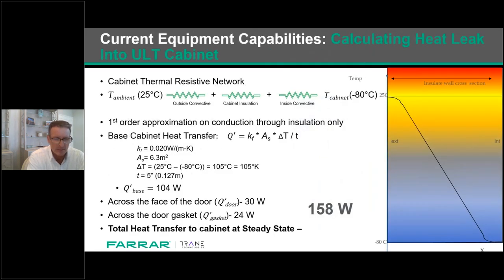So on this slide, we're going to go into the weeds. Where are we when we start calculating heat load? The following calculations were made from a 700 liter or 25 cubic foot ULT freezer. And this is where, you see at the top, we take into consideration the outside convection plus the cabinet insulation plus the inside convection in order to get to minus 80.